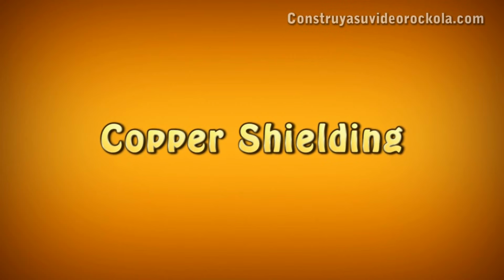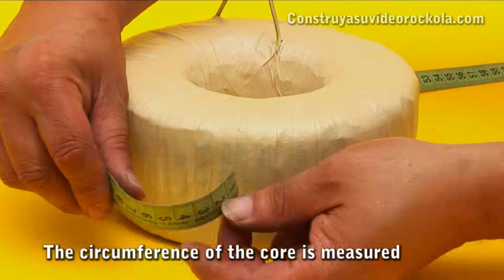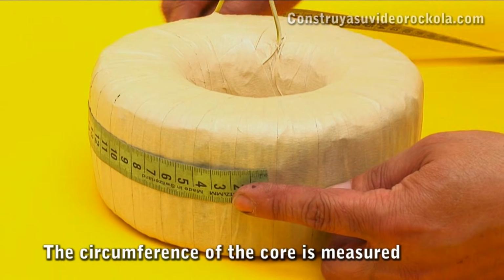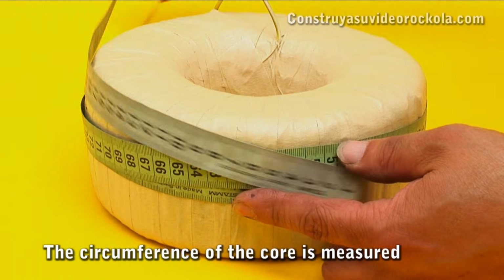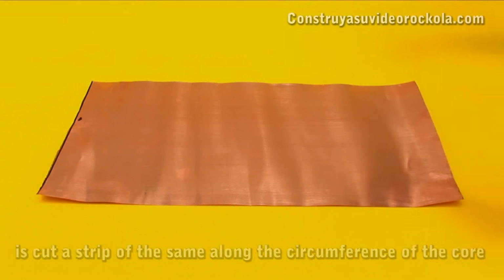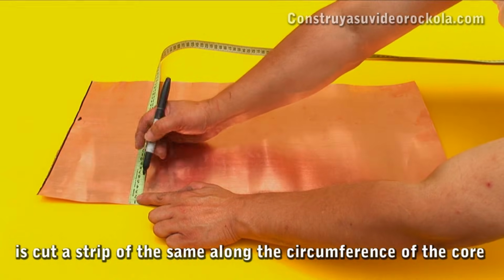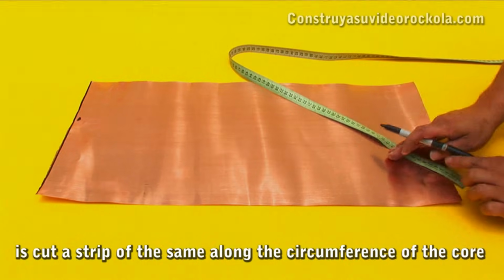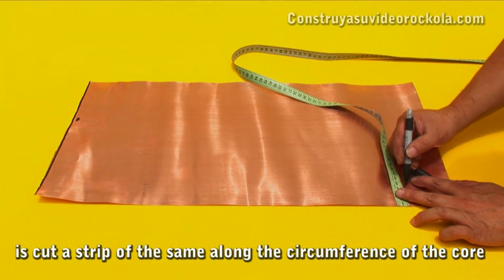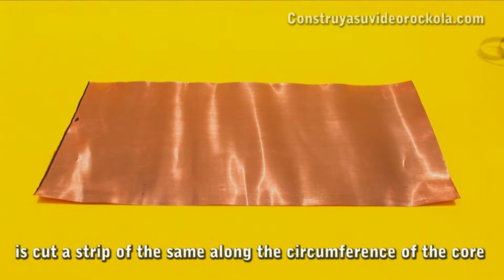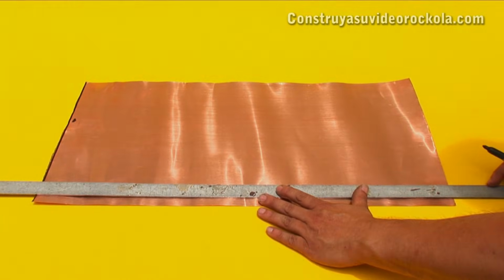Copper shielding. Now we place a copper shield that will be the ground. We measure the circumference of the core. We cut a strip of copper the same length as the circumference of the core, 2 cm less than the height of the core. In this case, it is 60 cm by 5 cm.